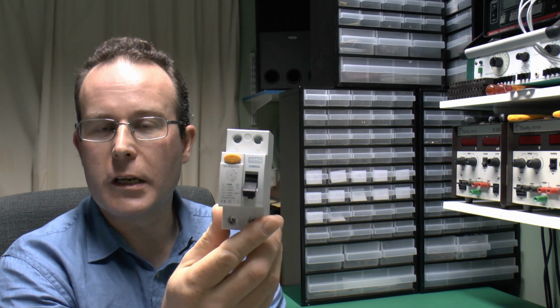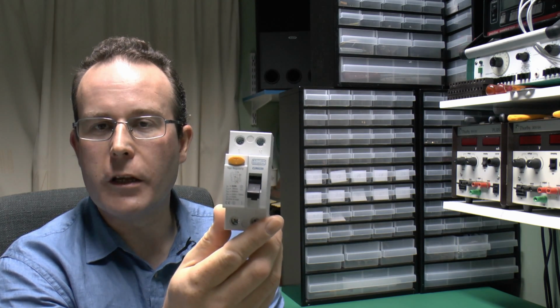And you can get ones lower than that, but they're not particularly commonly used, because there can be issues then with equipment and things causing trips anyhow, even when there's no fault. And larger values do also exist. 100 milliamp ones, for example, would be used in circumstances where the earth loop impedance is too high, typically if you've only got an earth rod at your earthing facility. And again, much higher ones are used for fire protection and in more specialised applications.